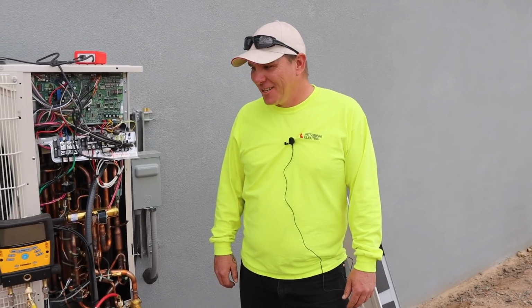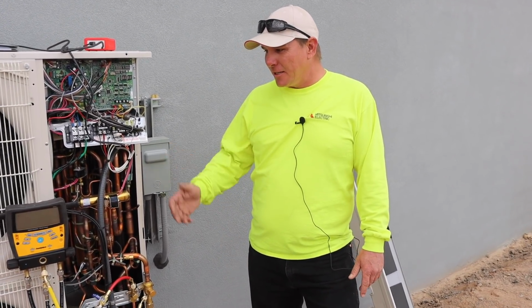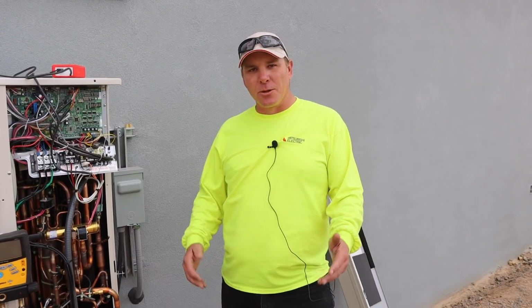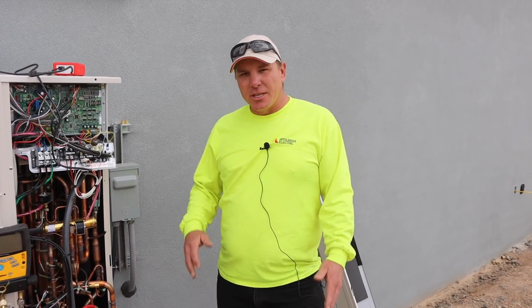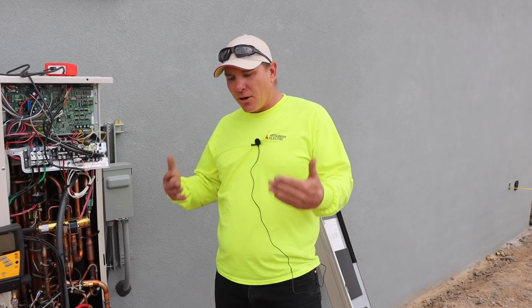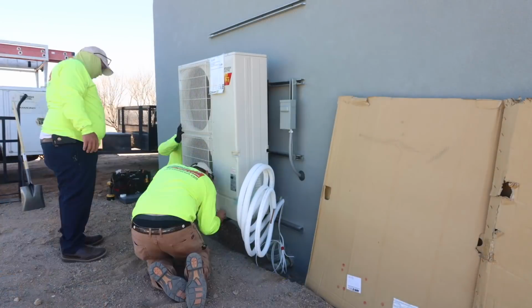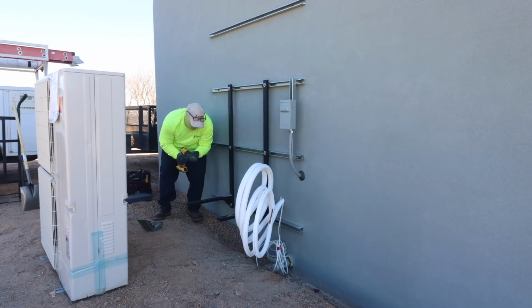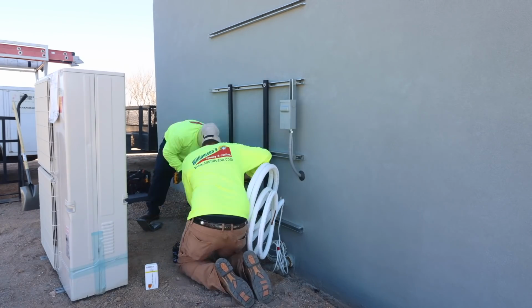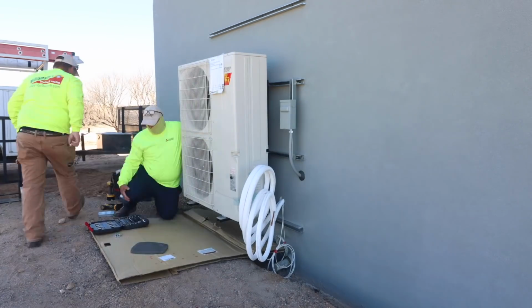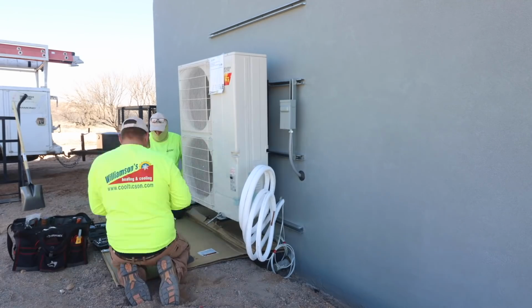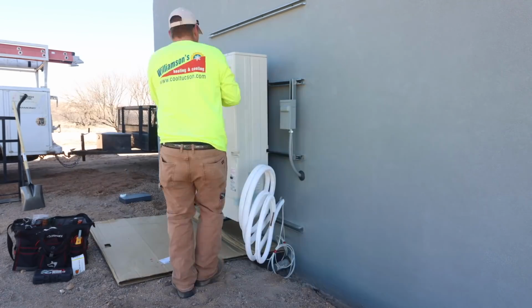That's right. So what we got here is the MXZ. It's actually a 3.5 ton multi-zone system. We just got everything installed, and right now we're starting the system up just to see how everything's operating. We just got done doing a pressure test. We got everything up to 650 PSI. We let that hold for roughly 3 hours. We had 0 pressure drop on it.